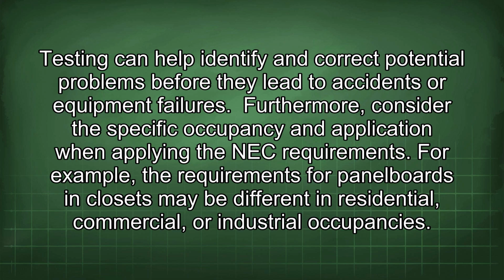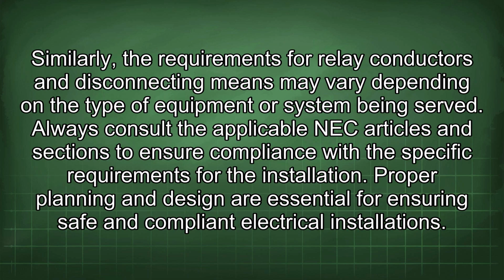Furthermore, consider the specific occupancy and application when applying the NEC requirements. For example, the requirements for panel boards in closets may be different in residential, commercial, or industrial occupancies. Similarly, the requirements for relay conductors and disconnecting means may vary depending on the type of equipment or system being served. Always consult the applicable NEC articles and sections to ensure compliance with the specific requirements for the installation.